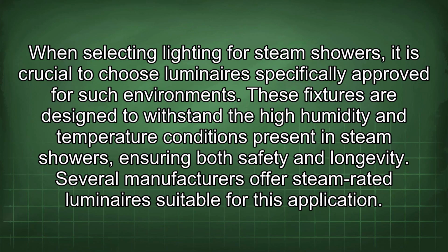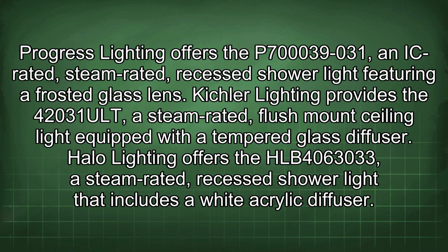When selecting lighting for steam showers, it is crucial to choose luminaires specifically approved for such environments. These fixtures are designed to withstand the high humidity and temperature conditions present in steam showers, ensuring both safety and longevity. Several manufacturers offer steam-rated luminaires suitable for this application. Progress Lighting offers the P700039-031, an IC-rated, steam-rated, recessed shower light featuring a frosted glass lens.